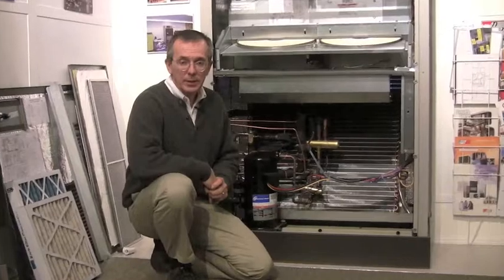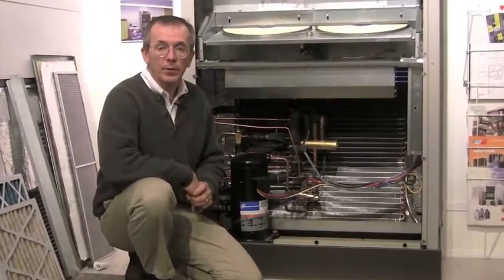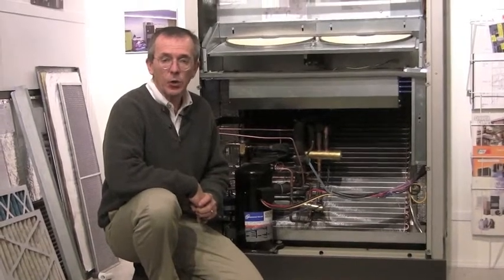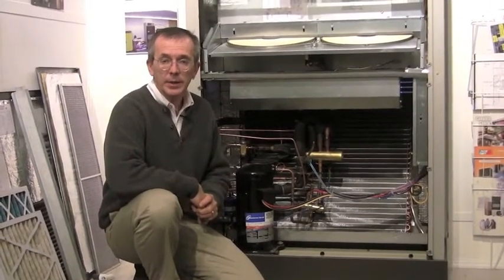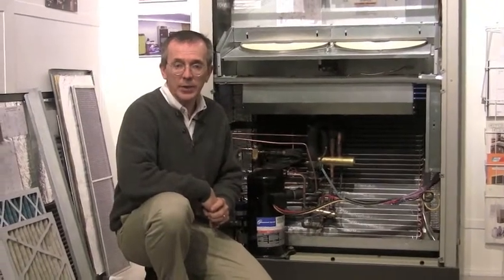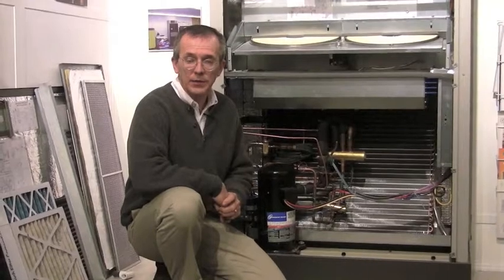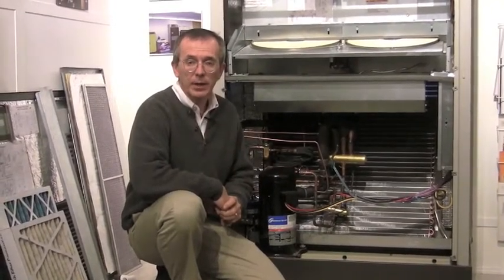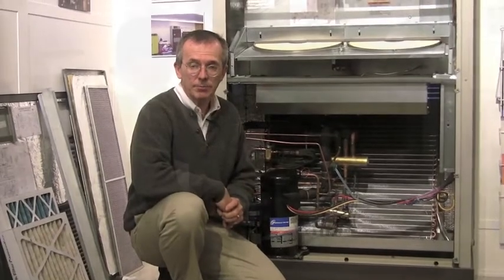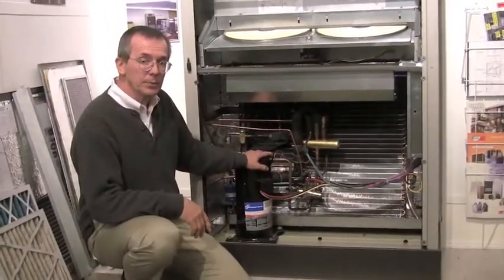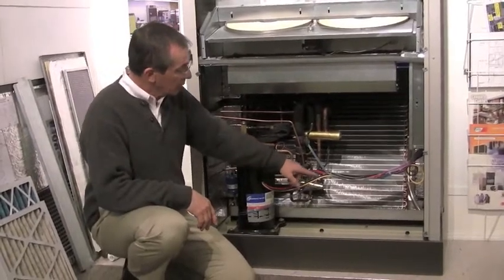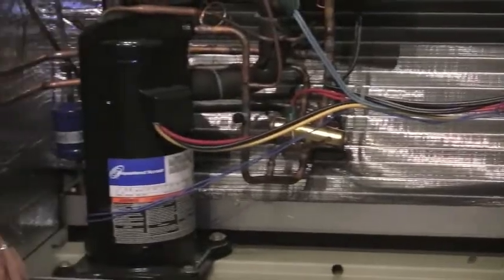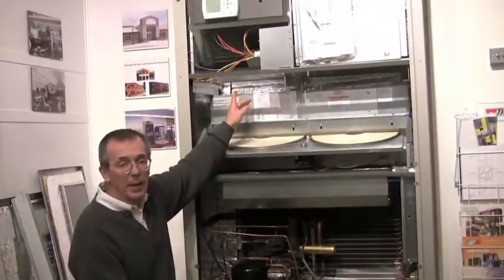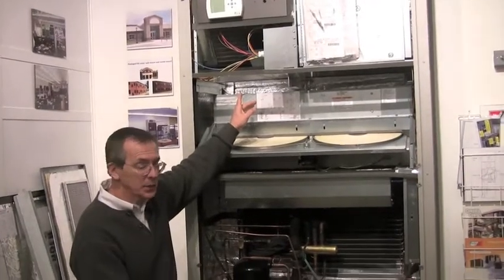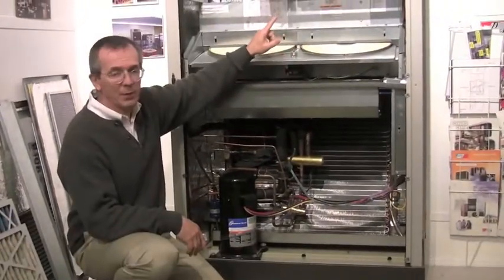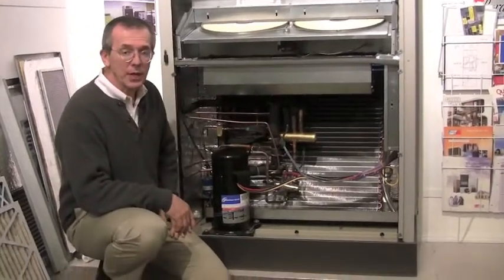Dehumidification will take precedence over heating. However, if you're in the dehumidification mode and you have a second call for heat, dehumidification will be de-energized and the unit will go back to heating. Once heating is satisfied, and if you still need to dehumidify, the unit will go back into dehumidification. Once again, this is a Copeland scroll compressor. Also in the compressor section, of course, is the condenser drain pan. It is stainless steel, and also the evaporator pan up and towards the top of the unit is stainless steel. There's also a tube that comes from the evaporator pan down into the compressor section.